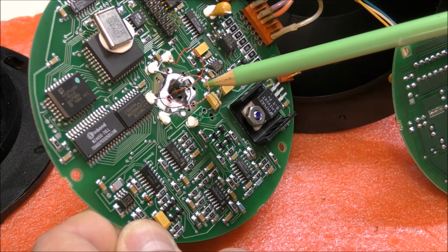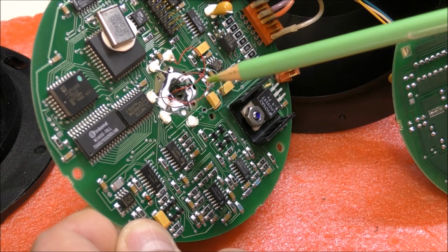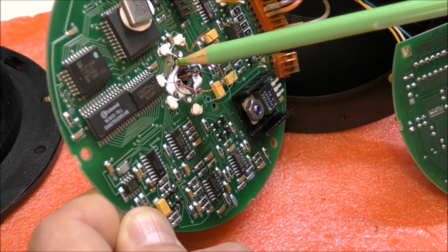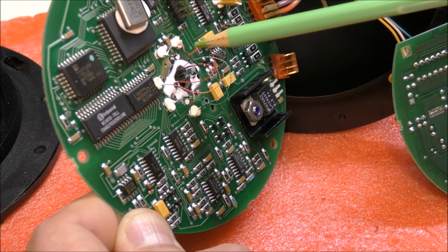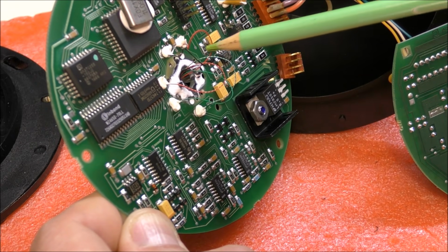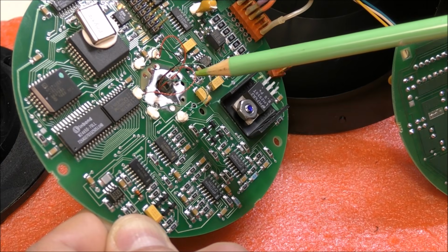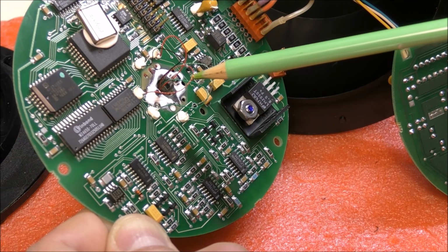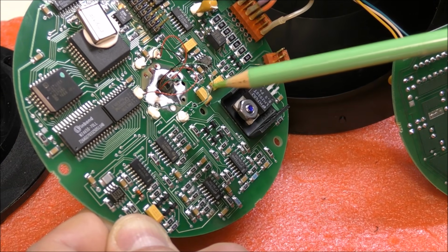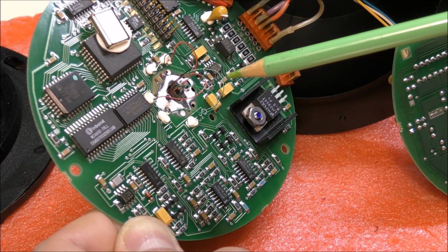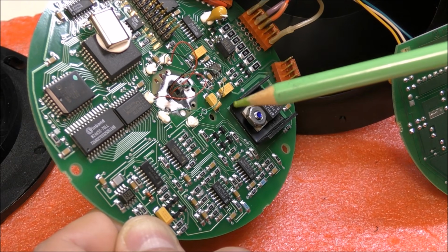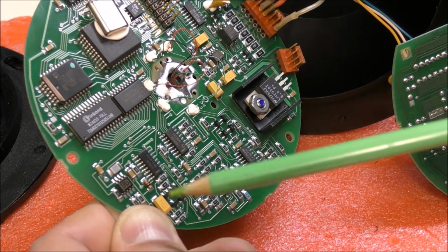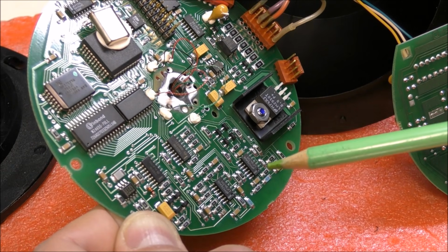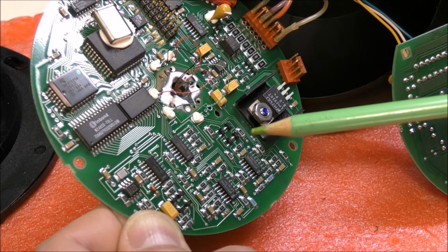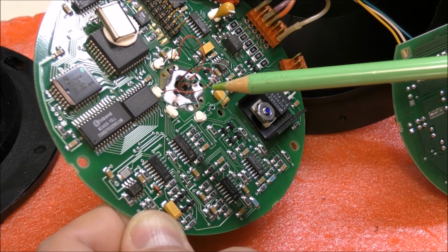We can see here in the center the connection of the flux gate sensor. You can see that we have 2 connections here, black and red. This should be the excitation coil. And we have here the connection to the pickup coils X and Y. Generally, the detection uses a synchronous detector. This is probably this circuit here. The synchronous detection works at a frequency which is twice the excitation frequency.